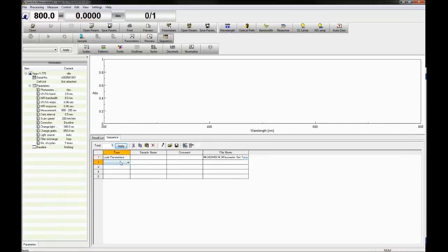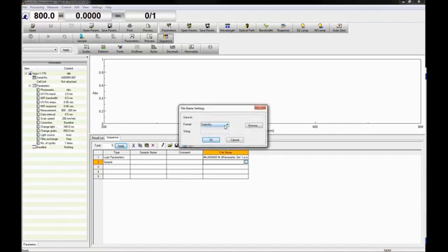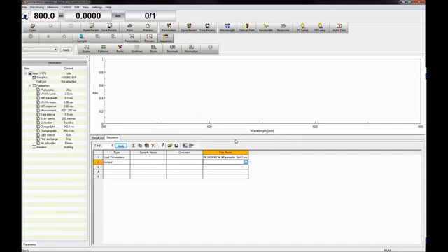If sample is selected for the type of measurement, the folder location where the sample measurement will be saved can be specified. Click the corresponding cell in the file name column and then click the button to the right. Choose the folder location and format of the file you would like to save. The baseline data cannot be automatically saved, and if a baseline is measured during a sequence, baseline or baseline dark must be selected in the parameters dialog box.